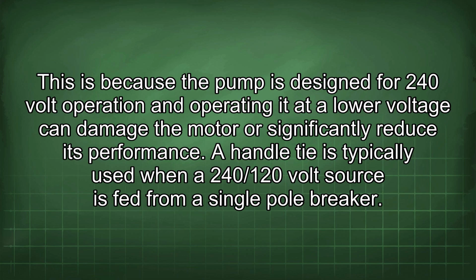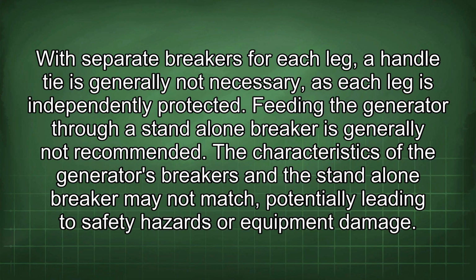A handle tie is typically used when a 240/120-volt source is fed from a single pole breaker. With separate breakers for each leg, a handle tie is generally not necessary, as each leg is independently protected. Feeding the generator through a stand-alone breaker is generally not recommended. The characteristics of the generator's breakers and the stand-alone breaker may not match, potentially leading to safety hazards or equipment damage.